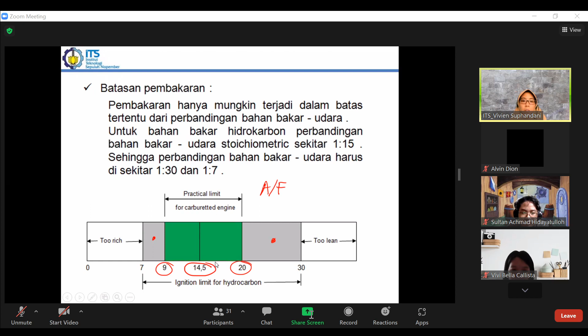If it's too high, this is the ignition limit, and this is the practical limit. So what if you have an air fuel ratio less than 9? It's still possible, but it's not practical anymore. And also here, we can still burn it, but it's not practical. Too lean or too rich, we cannot burn it. So practically, the air fuel ratio is around 9 to 20, which is the practical limit. Usually around this value.